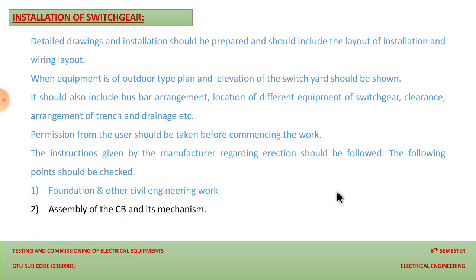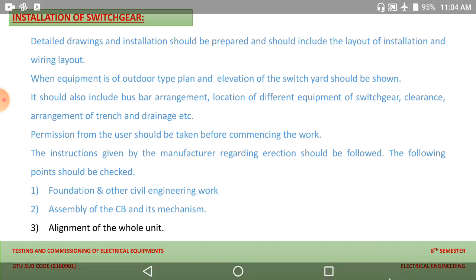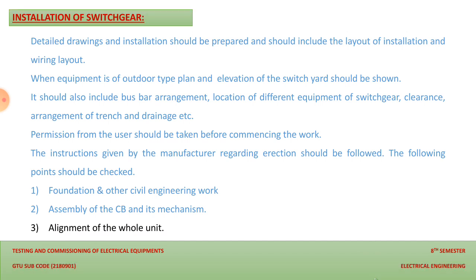The second thing is assembly of circuit breaker and its mechanism. The parts required for assembling the circuit breaker should be available for the switchgear that we are installing at the premises. And the third point is alignment of the whole unit. According to the standards, we have to maintain the alignment of devices, because alignment will be helpful for further maintenance and to examine the switchgear from the outer side. So alignment is most necessary. According to the standard alignment requirement, we should install our switchgear.